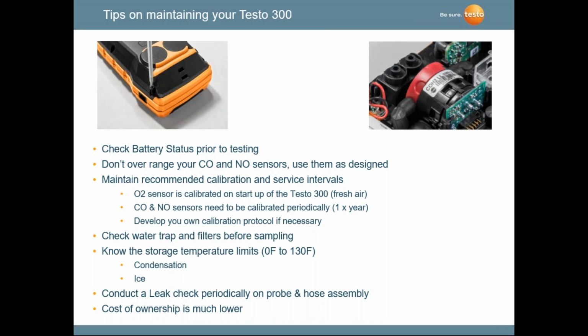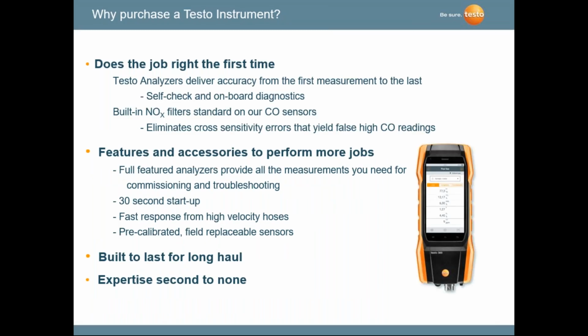And as you'll see with Testo, cost of ownership is very, very low. Calibration, but sensors today do not need to be replaced every year. If you're replacing sensors every year, whether it's an O2 or a carbon monoxide sensor, it's something you're doing with the instrument, or it's probably not a Testo instrument. Taking care of these sensors, they can last 4 to 6 years before you replace them.